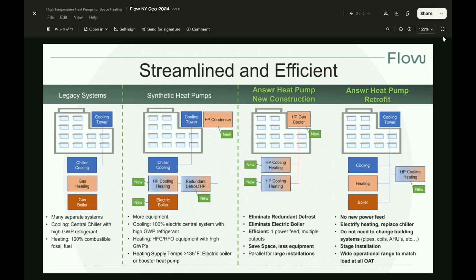Another really big benefit that comes out of all this: if you can do the simultaneous no-reversing element, you don't always need a new power feed. Oftentimes you have enough power hooked up for a chiller or cooling or your existing geo side that you can minimize your well and minimize your power feed coming into the space, avoiding that big infrastructure adder and making something better.